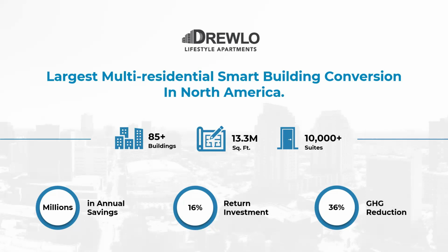Well, I would argue the opposite of that. And the reason is, just using some round numbers here, if you drive 30% of your heating load out of the building through optimization, and then use that real data to inform the size of the low or zero carbon heating plant that you're going to build eventually, you've just reduced the size of that investment on the far side. That's fundamentally, in my opinion and Nerva's opinion, why optimization has to be first.